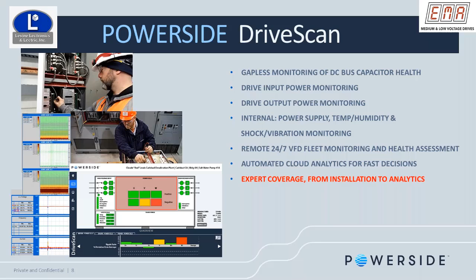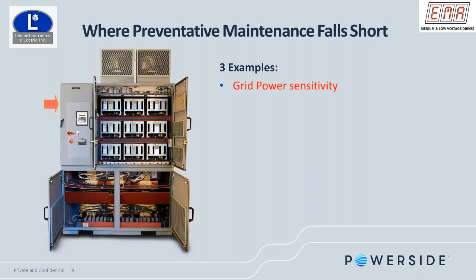On the grid side, if you ever have the Siemens medium voltage drive, this is a 1,000 horsepower frame, Gen 4. This is how it looks, right? So we have our phase shifting transformer, so we can look at the input current here. We can look at our input voltage coming from the grid and see if there's any problem as far as power quality coming in. We can look at our harmonics as well. We can look at the DC bus capacitors and the health of the power modules.